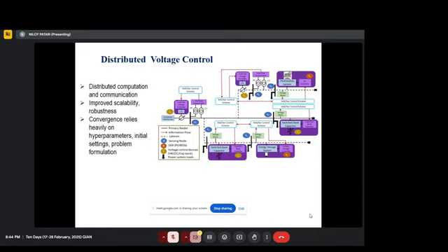So these kinds of set points can change, and if the capacitor banks which are on are changed, then the voltage will also change in the next instant. Because at 300 kVr, the voltage will be pretty high. At 200 kVr, the voltage will go down a bit.